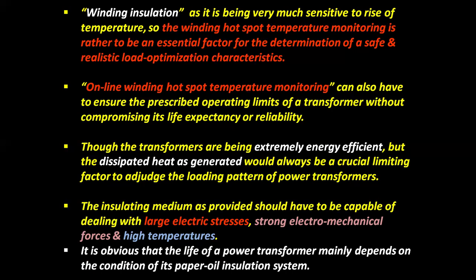Though transformers are extremely energy efficient, the dissipated heat generated is always a crucial limiting factor in judging the loading pattern of power transformers. The insulating medium provided should be capable of dealing with large electrical stresses, strong electromechanical forces, and high temperatures. It is obvious that the life of a power transformer mainly depends on the condition of its paper oil insulation system.